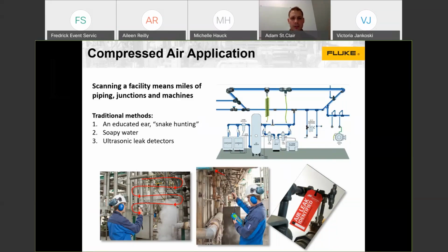And then finally, ultrasonic leak detectors. This is the pictures you're seeing on the bottom of the slide here, somebody using a conventional ultrasonic leak detector, which is a microphone and some headphones. You go and scan all of the areas where there could possibly be leaks, listening for that sound profile that would indicate there's a compressed air, gas, or vacuum leak.